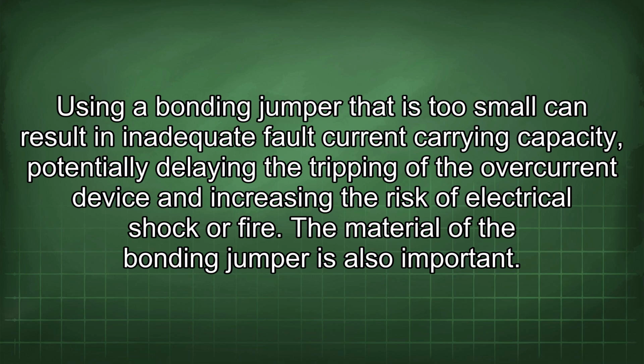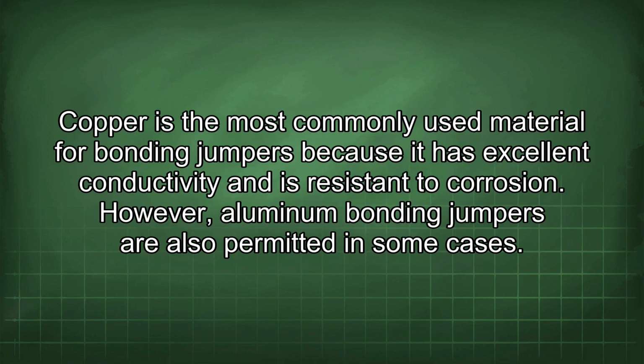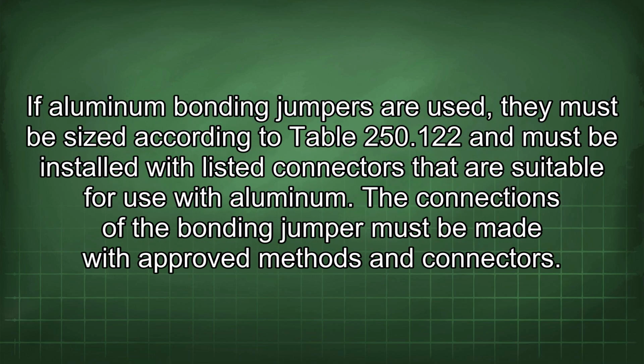The material of the bonding jumper is also important. Copper is the most commonly used material for bonding jumpers because it has excellent conductivity and is resistant to corrosion. However, aluminum bonding jumpers are also permitted in some cases. If aluminum bonding jumpers are used, they must be sized according to Table 250.122 and must be installed with listed connectors that are suitable for use with aluminum.